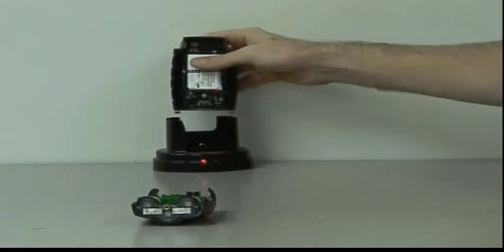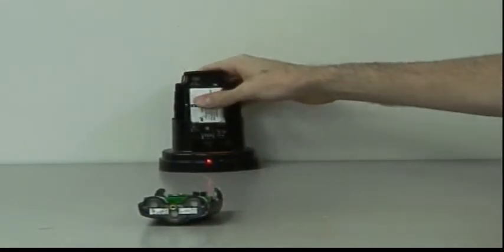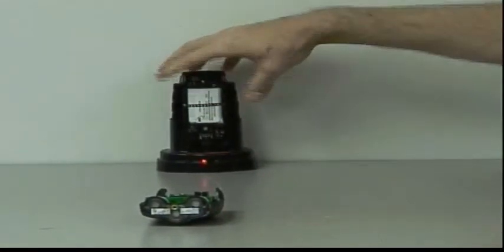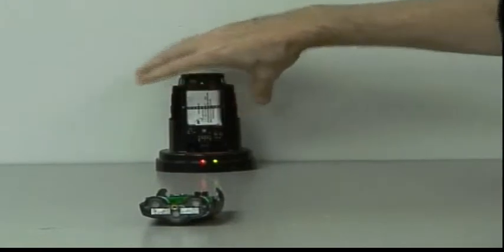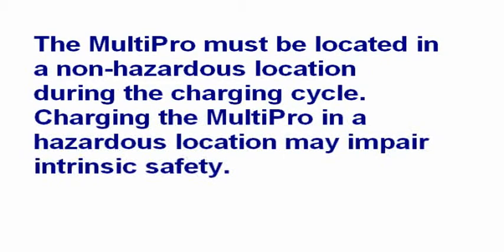The charger will completely recharge the lithium-ion battery pack in about 5 hours. The green charge LED on the right side of the charger is lit during the charging cycle. Once the battery is fully charged, the charge LED will turn off. Please note that the MultiPro must be located in a non-hazardous location during the charging cycle. Charging the MultiPro in a hazardous location may impair the intrinsic safety.